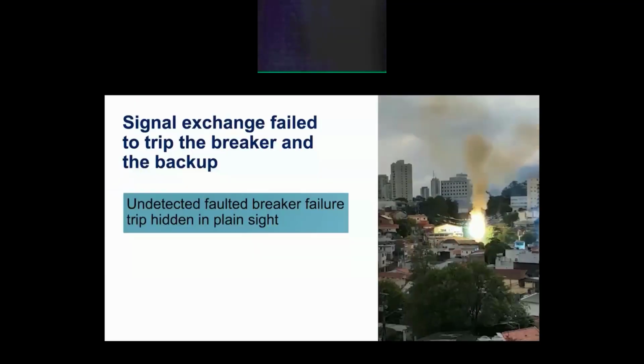But interrupted load is not enough to understand the true severity of failure. The Space Shuttle and 737 MAX illustrate catastrophic failures associated with the inappropriate use of technology and the incorrect categorization of severity of failure. Perhaps we should update categories in energy control systems to include cost in dollars and public safety. An unfortunate example happened in Hurricane Katrina, which provided a real-world example of the need for better metrics. Pendleton Methodist Hospital administration didn't evacuate, even though they knew the hurricane was approaching. The disaster plan managers said they had prepared for a utility blackout and they had bought a backup generator. However, those generators were in the basement and they were quickly flooded, and at least one patient died before they could evacuate. So the hospital actually needed better metrics and a correct severity classification to avoid the failure that was hidden in plain sight.